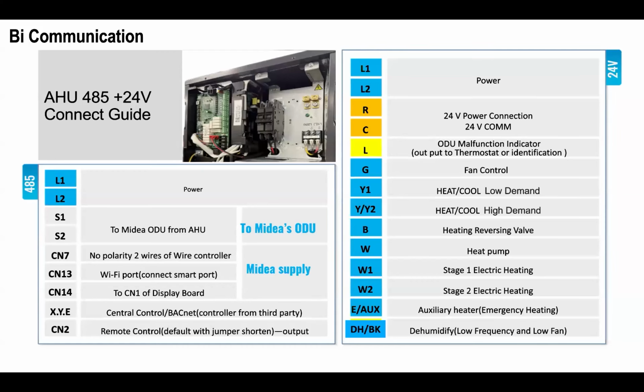CN7, which is right next to it, is your wiring for the non-polarity wire controller. Wire controller only takes 2 wires. It's HA and HB. S1 and S2 are polarity sensitive. So when you wire this, S1 has to go to S1 and S2 has to go to S2. If you crisscross them, it won't blow anything up. It just may not communicate.